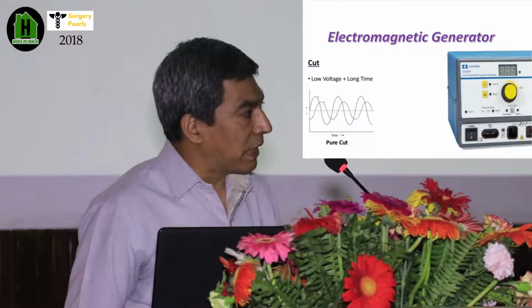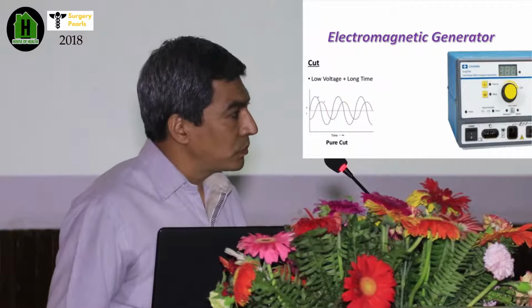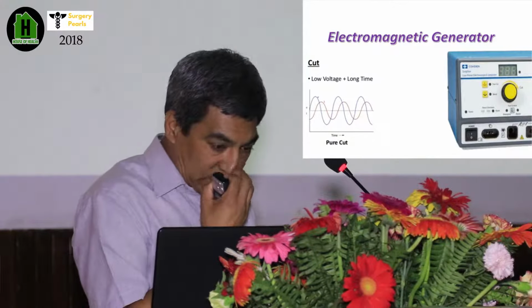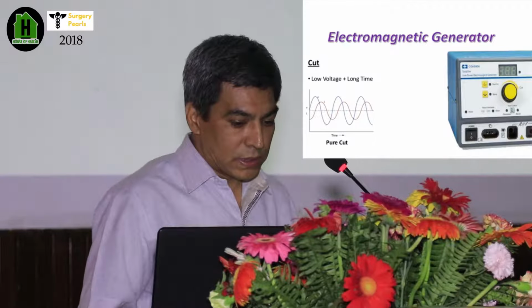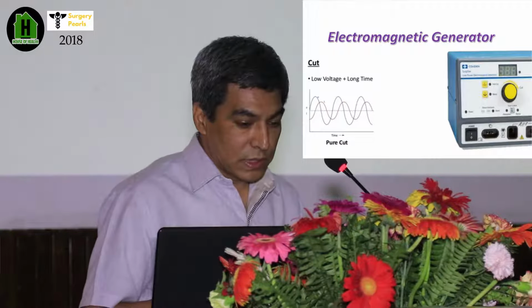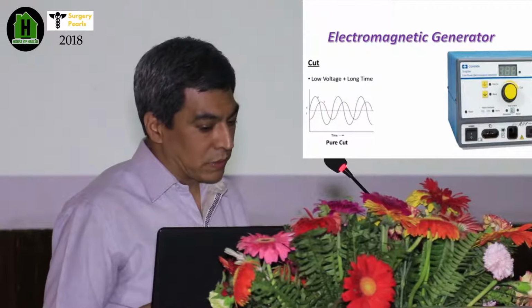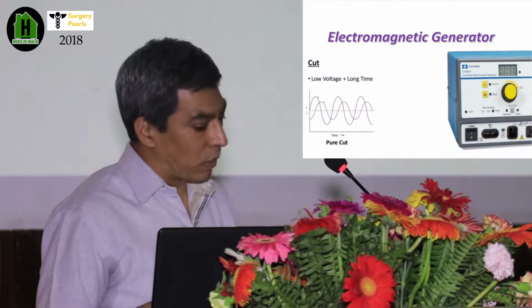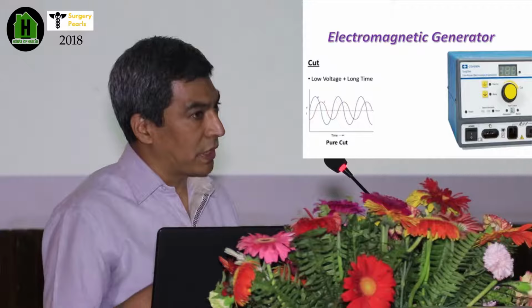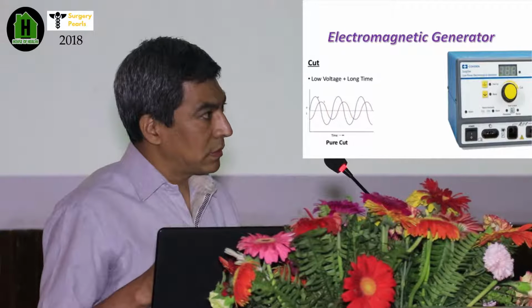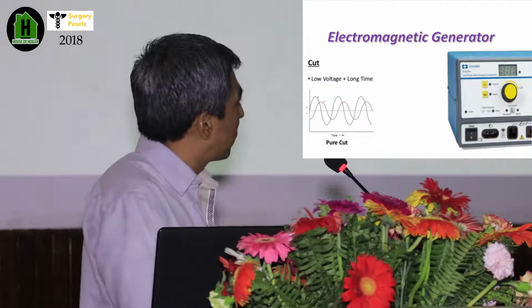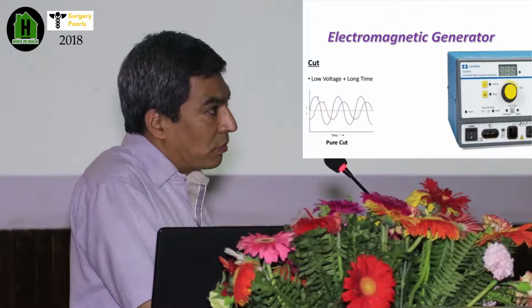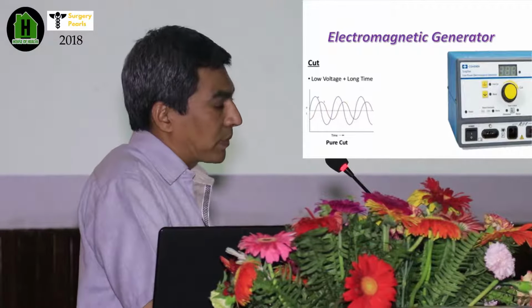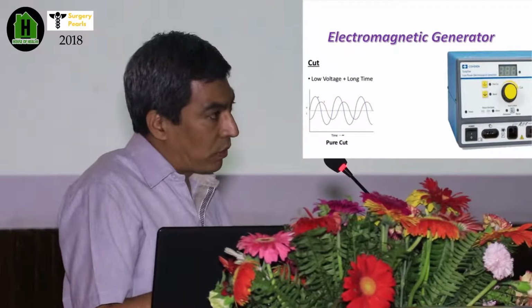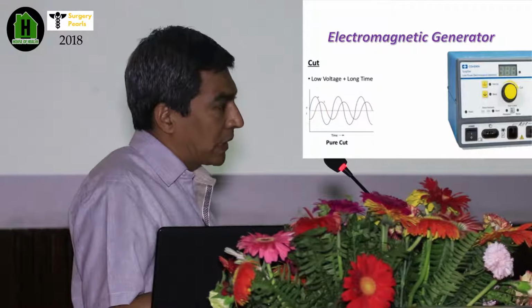So in this simple device, we have two different basic functions. One is the cut, as you know, cutting the tissues. In the cutting mode, it will run at a low voltage, but the duration will be very long, and it will be continuous. You can see from the graph here, the current will be continuous, uninterrupted. The voltage will be very low. It takes a long time to get the effect of cutting.